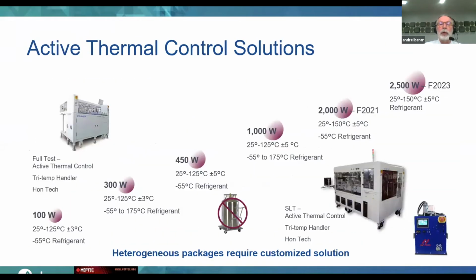On top of the thermal head, which is the part that makes contact with the device, we need to be able to remove the heat from the thermal head. There are a variety of active thermal control solutions that are ready for high volume manufacturing for final test, as well as system level test.